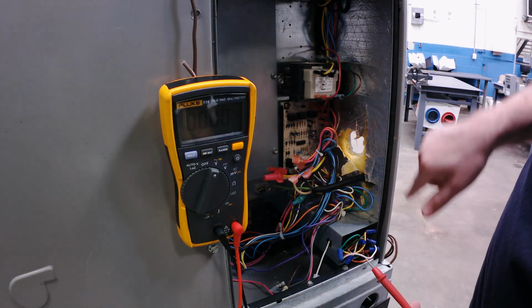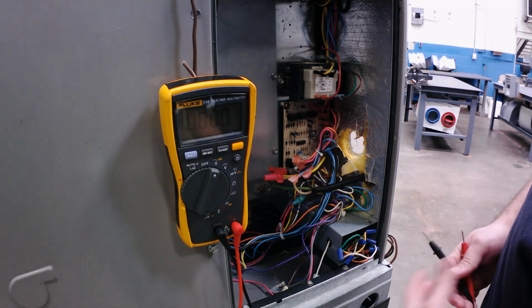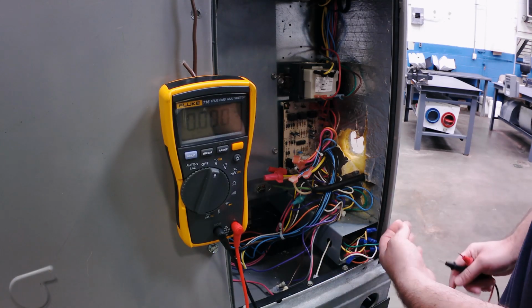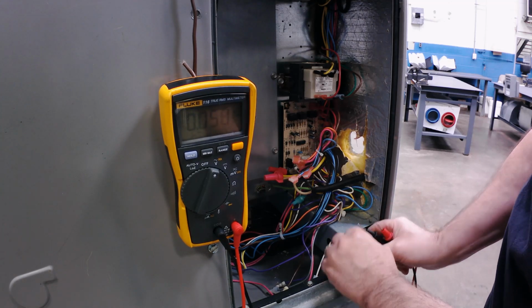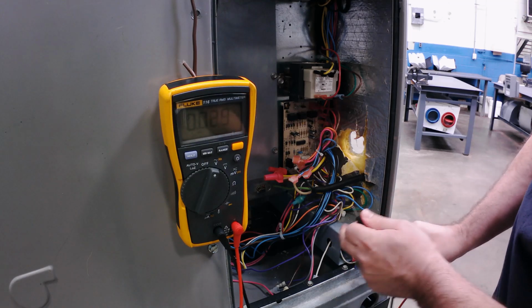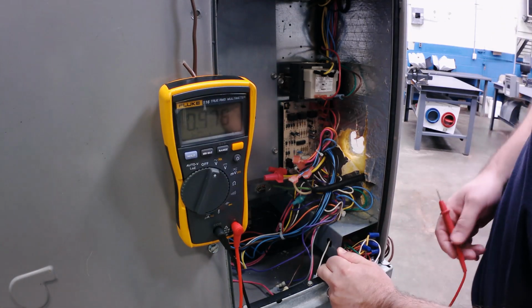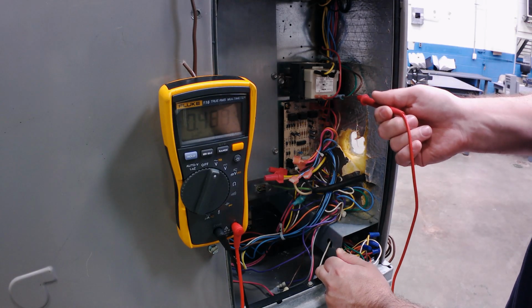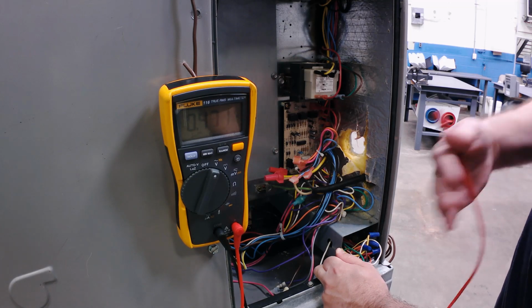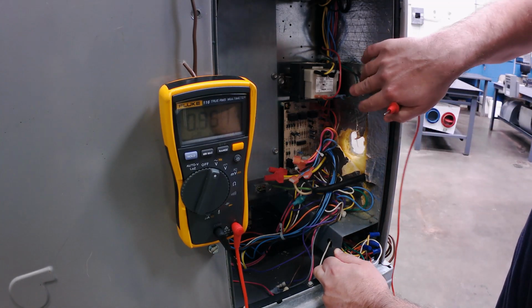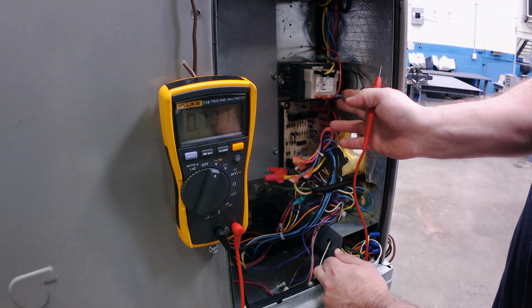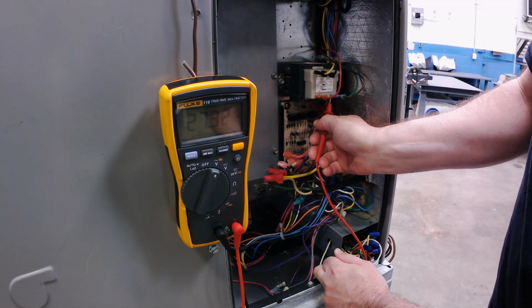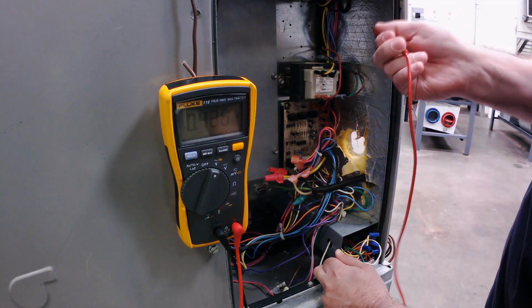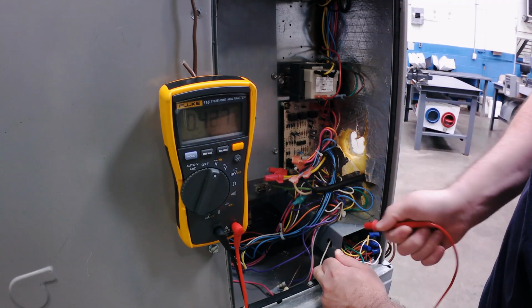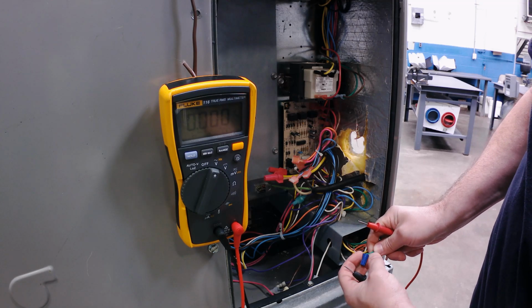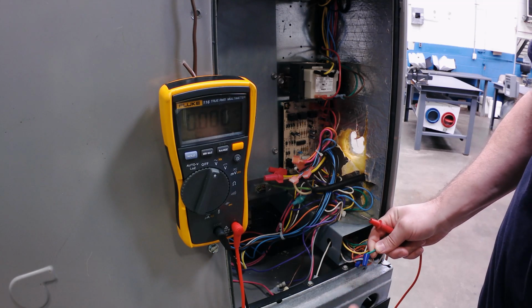Alright, so most of the time in the package unit you're going to have a little corner right here where all the low voltage is. So I'm going to undo the green wire, and I'm just going to expose that thermostat wire from the thermostat. So if I'm checking it, like I said, I'm going to grab that green wire here, and I'm going to look for common. Now usually what I would tell you is, don't worry about the common in the wire nuts if you're inside a package unit or the air handler. Try to find the common at the transformer. Sometimes you can just wiggle that little wire off of the common and check it there, and I've got 27 volts. So in this case, I know that my thermostat is sending power down G because I'm checking it at the first spot, the first connection where it goes from the field wiring into the factory wiring.